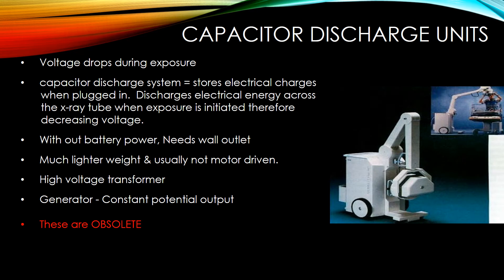Capacitor discharge units: the voltage drops during exposure. A capacitor discharge system stores electrical charges when plugged in and discharges electrical energy across the x-ray tube when the exposure is initiated, therefore decreasing voltage. Without battery power, it needs a wall outlet. These units are much lighter and usually not motor driven, so they were hard to push. They use a high voltage transformer with a generator with constant potential output. These are now obsolete.